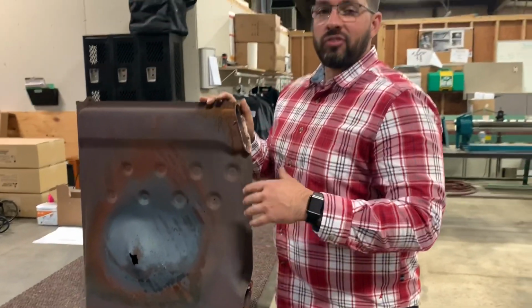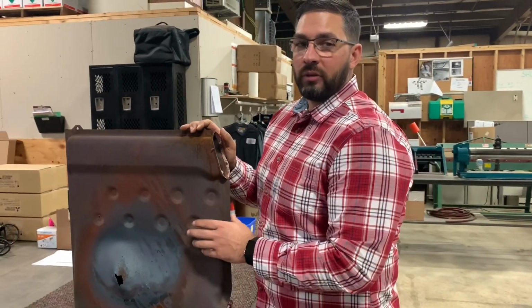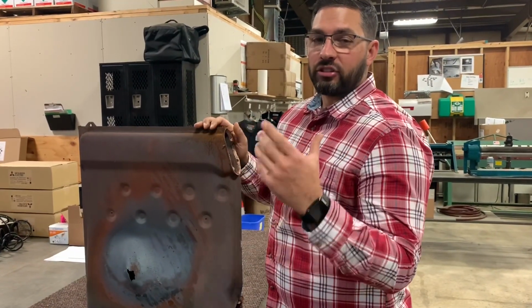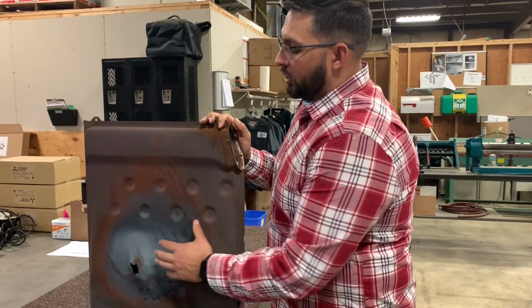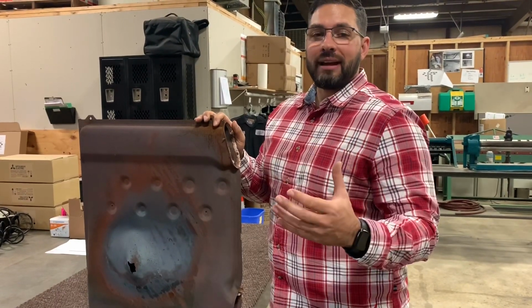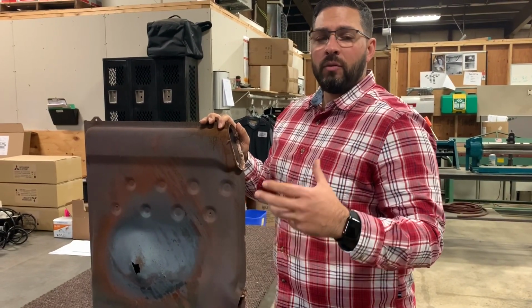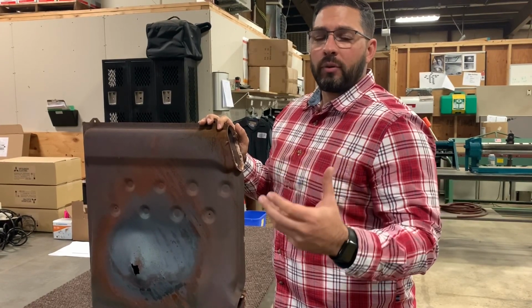This furnace is about 30 plus years old. The customer didn't know this was going on in their house—it was actually a service call. We went out there, diagnosed this cracked heat exchanger, and immediately got them a replacement.